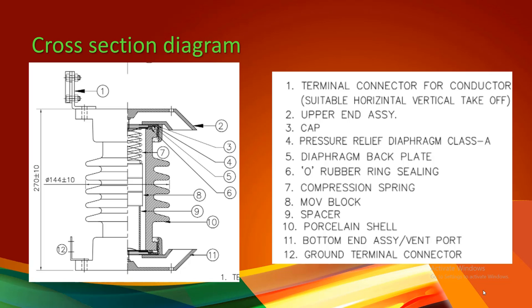There is a pressure relief diaphragm — class A or class B. When the pressure increases inside the surge arrester, the diaphragm releases that pressure. The diaphragm has a pin-type arrangement; when pressure increases, the pin-type structure breaks and releases the pressure.